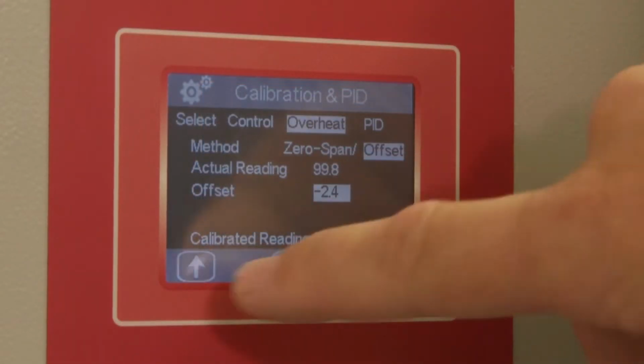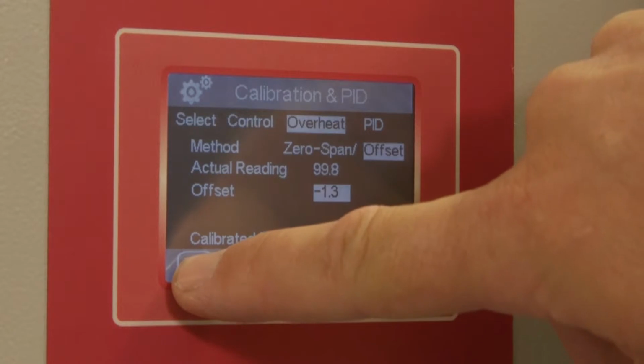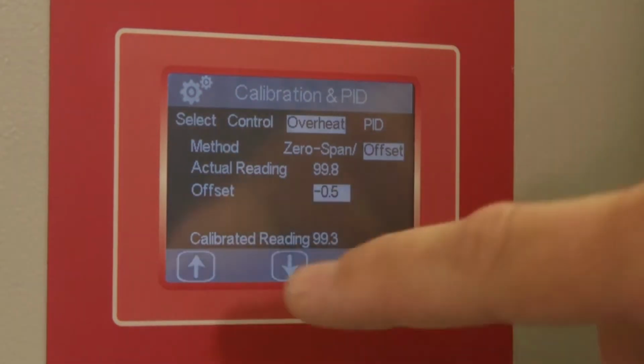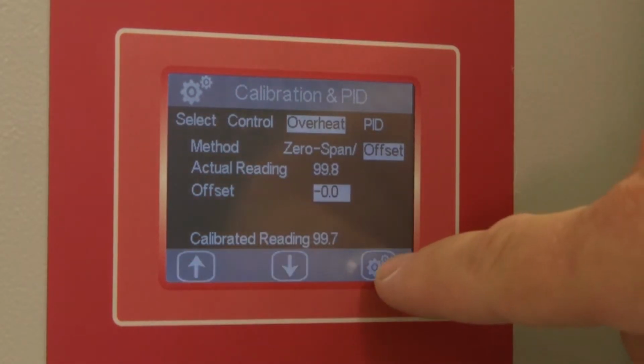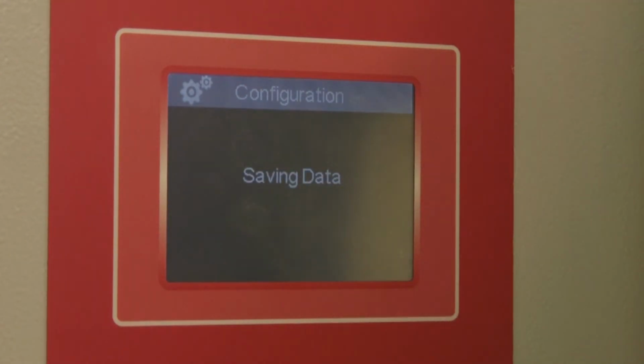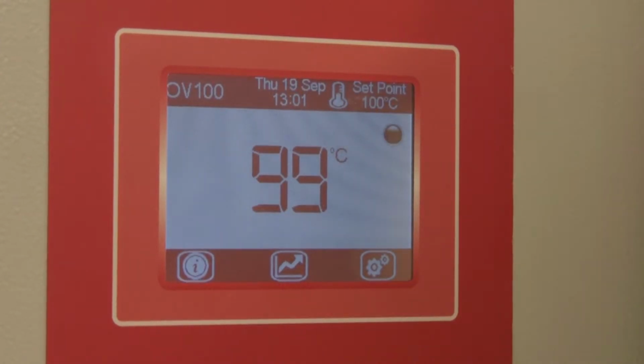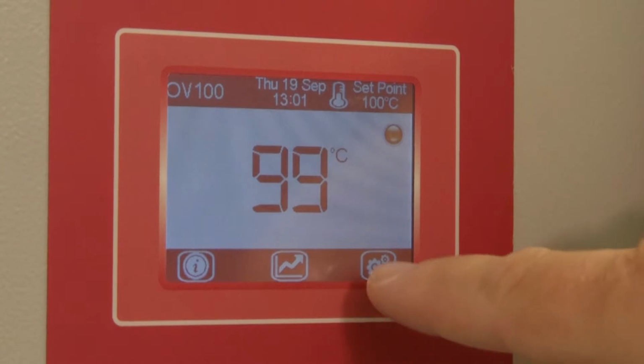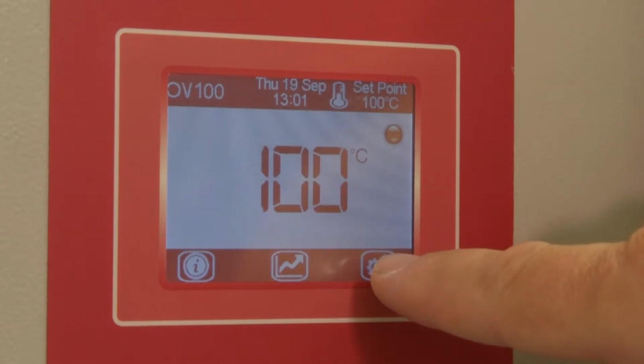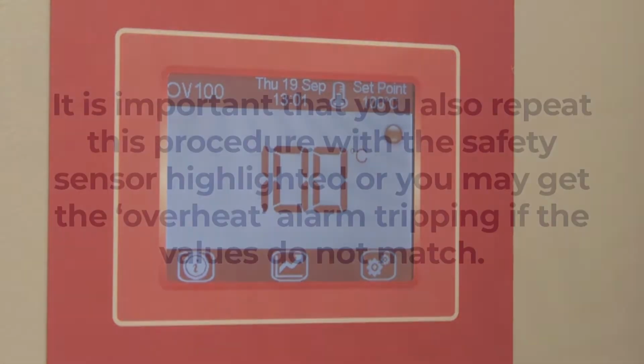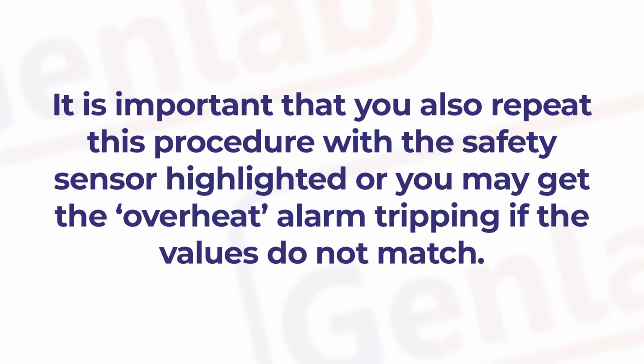All ovens have a second sensor to control the overheat protection. Press the Overheat tab and repeat the procedure. To accept these changes, press the Config icon, then Home, and accept these changes. It is important that you also repeat this procedure with the safety sensor highlighted, or you may get the overheat alarm tripping if the values do not match.